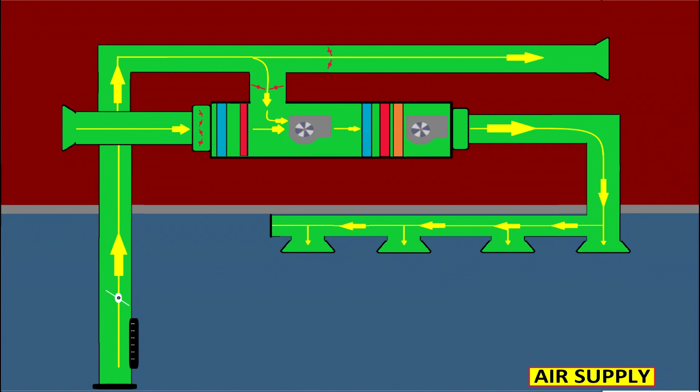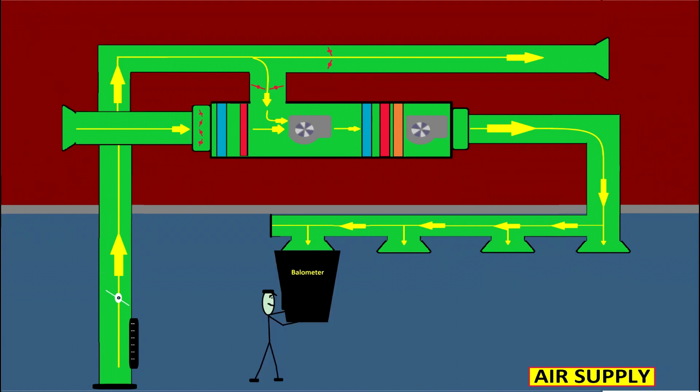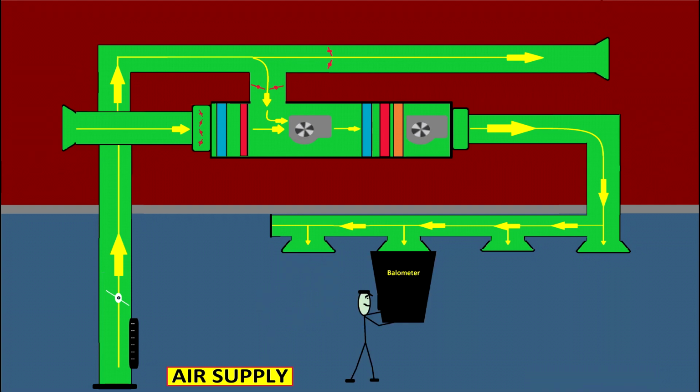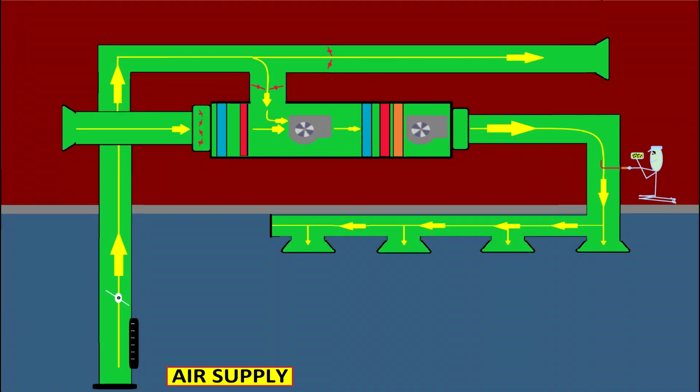If you remember, I talked before about taking measurements from multiple locations. So here, if we use a balometer, we take the measurements from inside the rooms, and then the sum of all these outlets should be equal to the measurement I'm doing now on the supply air duct. Or if I have some losses, then I have to subtract that value. I like to take some readings from the air that is extracted from the rooms or from the fresh air intake duct. Also, I would like to take readings from the exhaust. I always want to know as much as I can about my AHU.